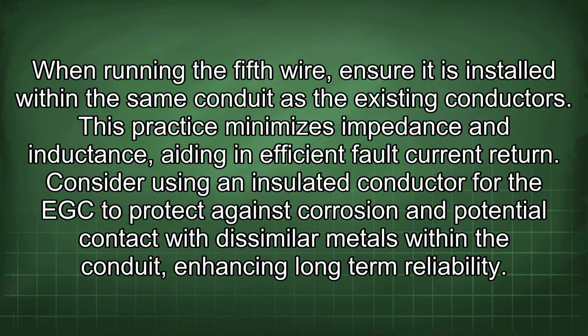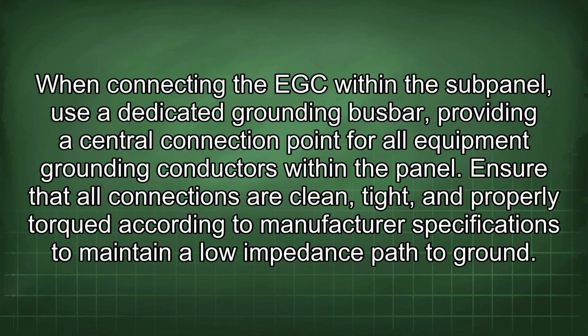When running the fifth wire, ensure it is installed within the same conduit as the existing conductors. This practice minimizes impedance and inductance, aiding in efficient fault current return. Consider using an insulated conductor for the EGC to protect against corrosion and potential contact with dissimilar metals within the conduit, enhancing long-term reliability. When connecting the EGC within the subpanel, use a dedicated grounding busbar, providing a central connection point for all equipment grounding conductors within the panel. Ensure that all connections are clean, tight, and properly torqued according to manufacturer specifications to maintain a low impedance path to ground.